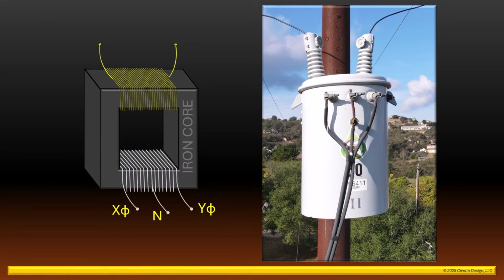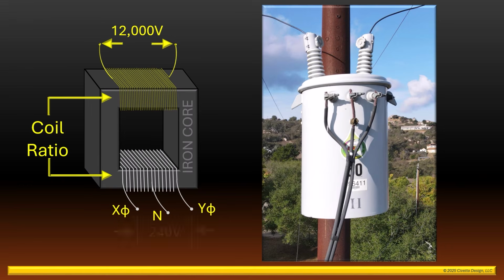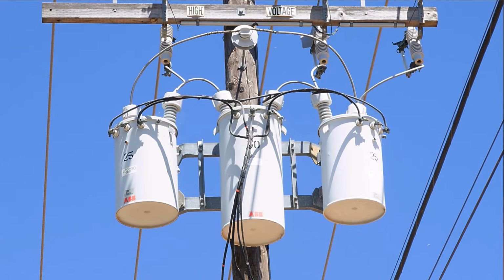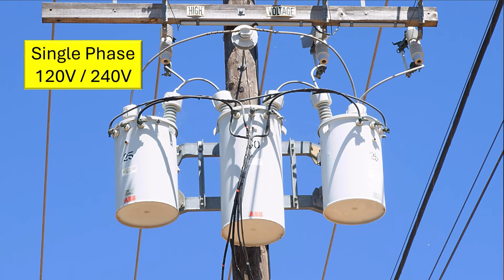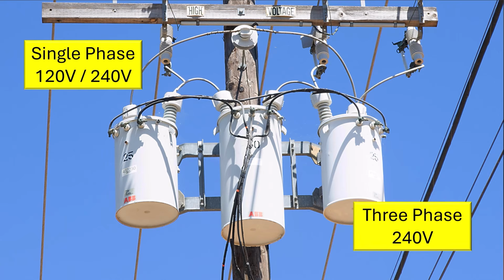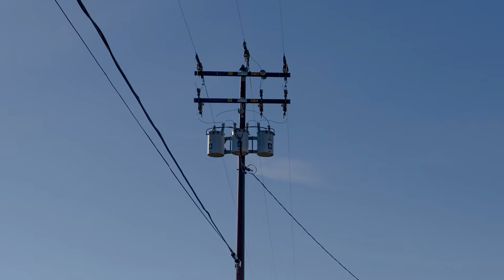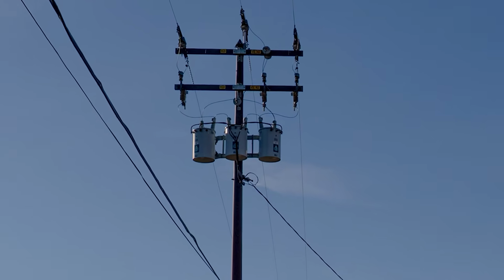When a voltage of 12,000 volts is applied to the primary leads, this transformer has the proper coil ratio to produce a secondary voltage of 240 volts between the two outer phases and 120 volts between either phase and the neutral. For the remainder of this video, we're going to show how to use this exact same transformer to create a three-phase transformer bank like this one, capable of producing single-phase 120 and 240 volts, as well as three-phase 240 volt power.